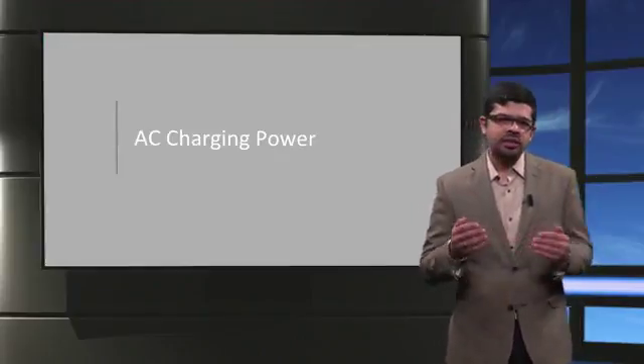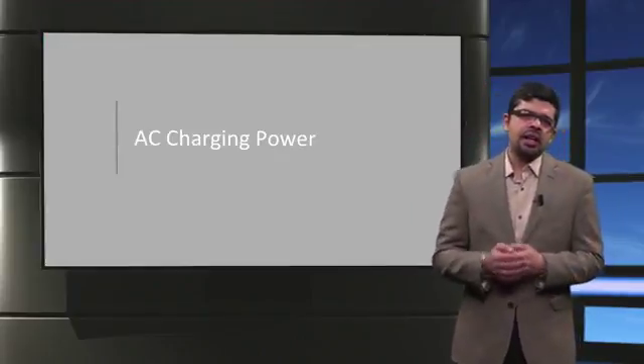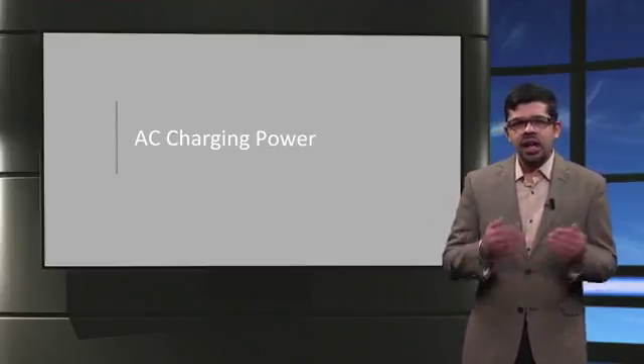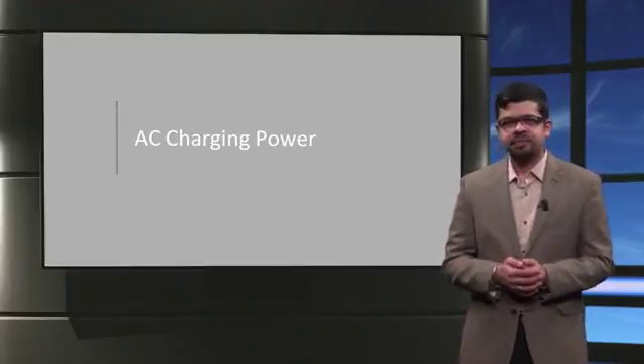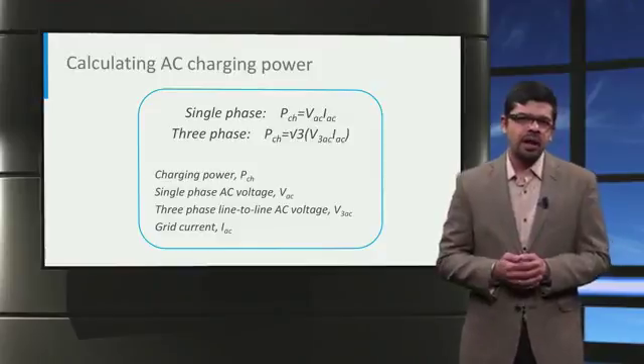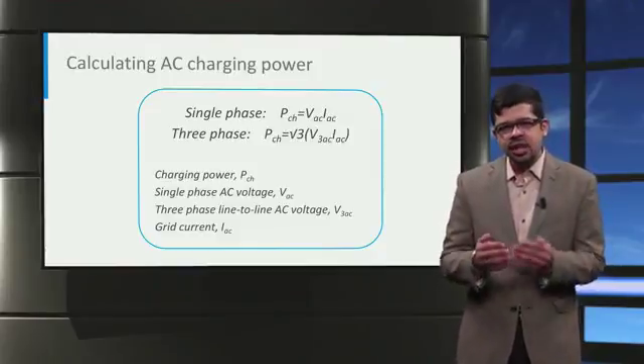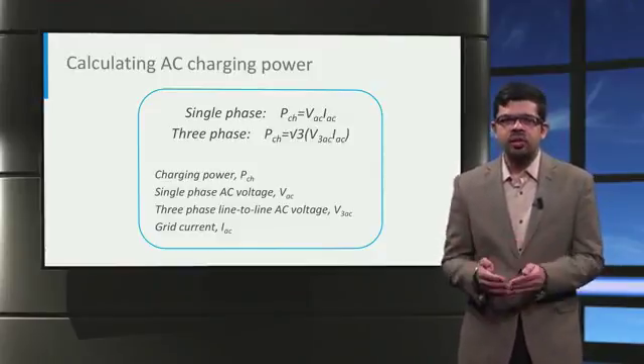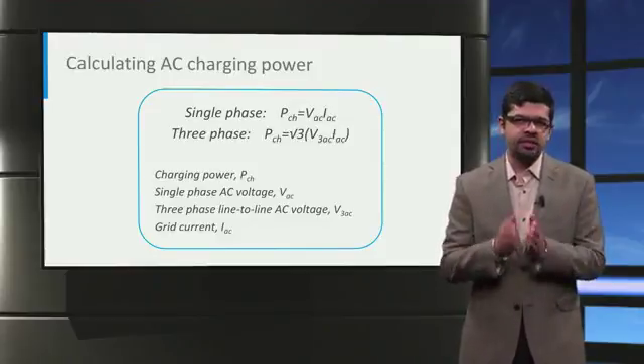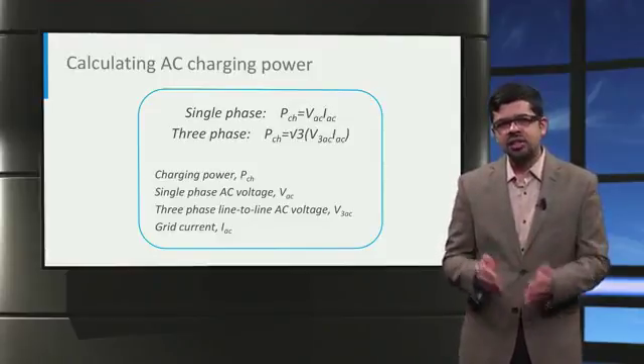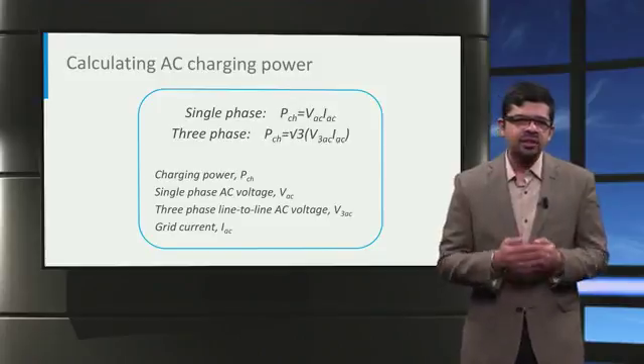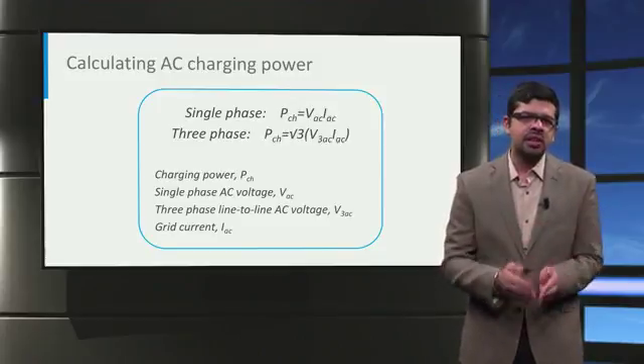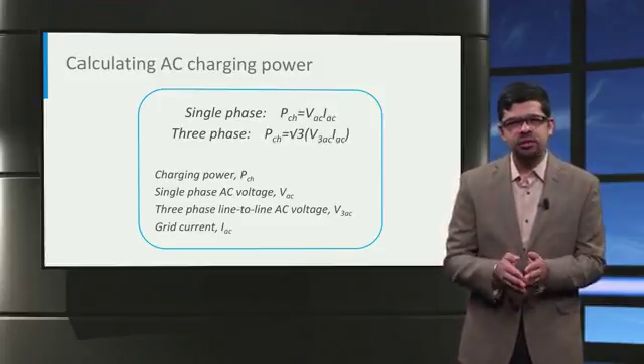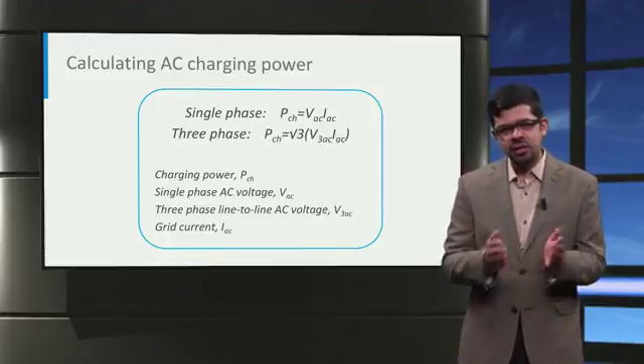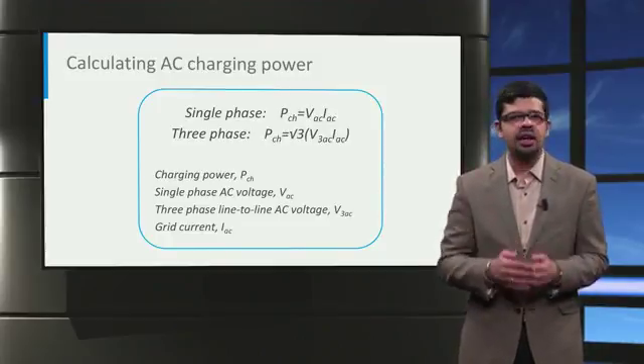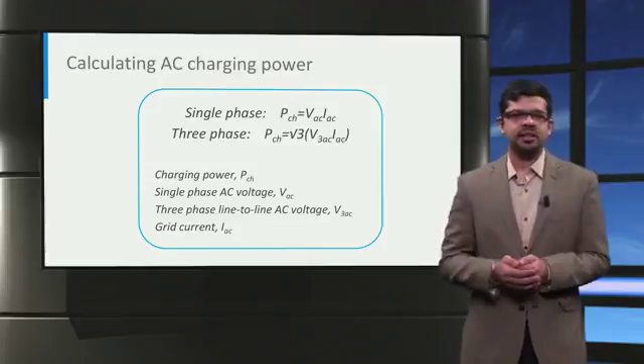Now that you have seen the different AC charger types, let us look at how we can calculate the AC charging power. This is quite simple. The single phase AC charging power is the product of the single phase AC voltage VAC and the grid current IAC. The 3-phase AC charging power is calculated as root 3 times the product of the line to line 3-phase AC voltage V3AC and the grid current IAC.